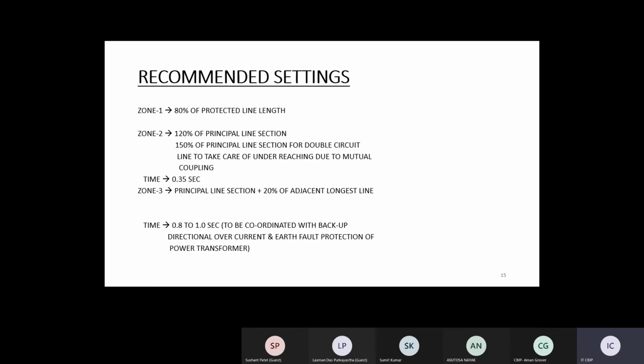But one thing you should know, that zero sequence and mutual impedance is quite a high figure. This zero sequence and mutual impedance, you need to know. Otherwise, there's zone two. The zone two, 150%. I said that, where is the pointer? Pointer is not here. Okay. Because of the effect of zero sequence and mutual impedance, this 150% has been kept.